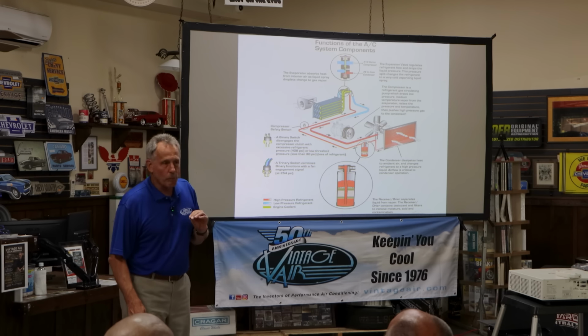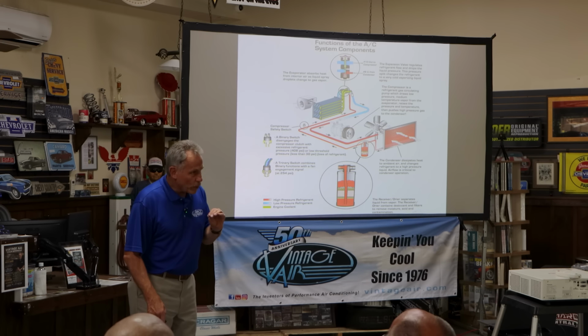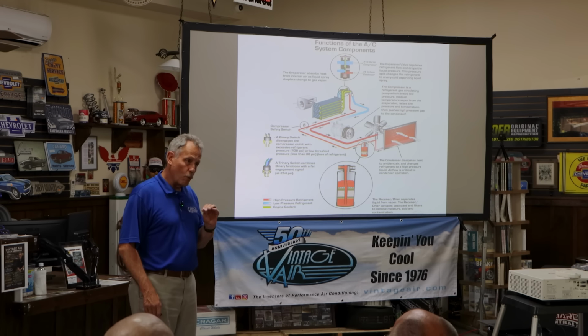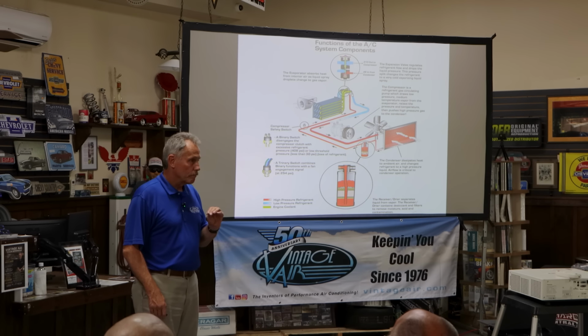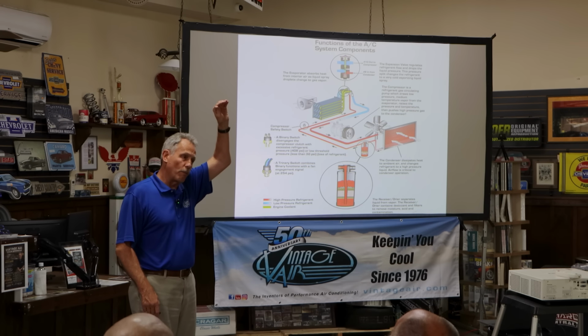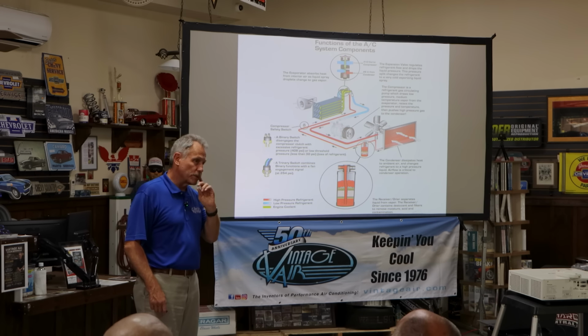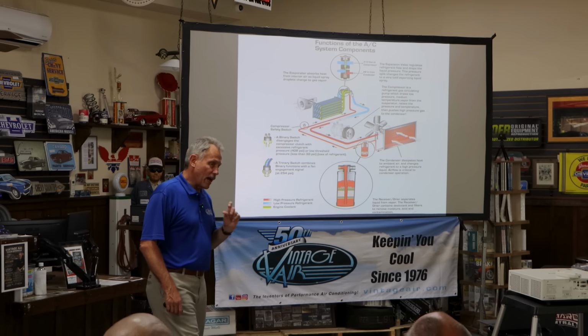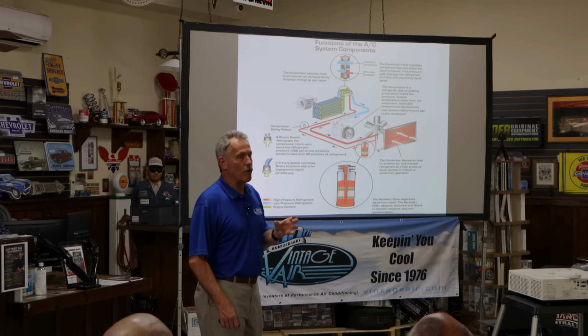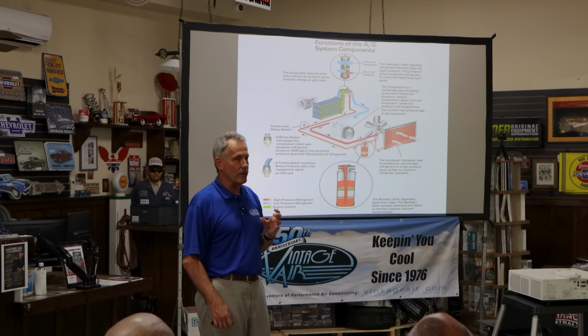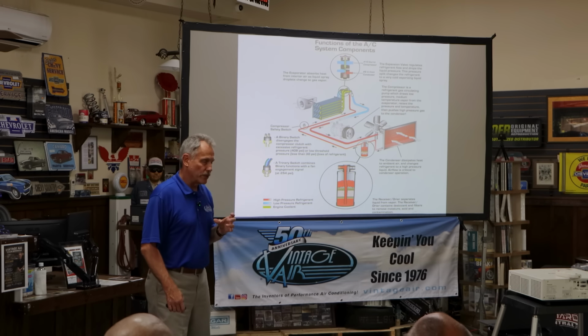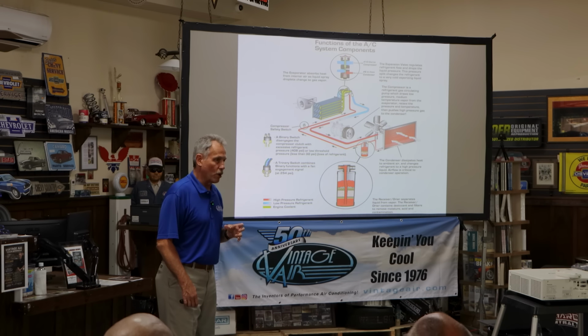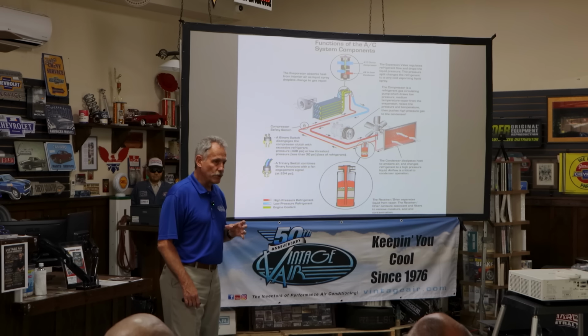When we say 1.8, I mean 1.7 pounds to 1.8, it's got to be there. Any more than that, you lose performance. Any less than that, you lose performance. You got to use the right amount. If you don't have a quality scale or a charging station or something like that, you're not going to charge that system as properly as it should be charged. You got to use the right amount of it.